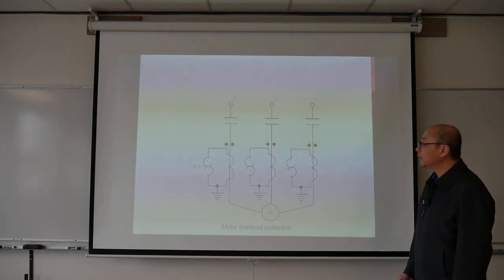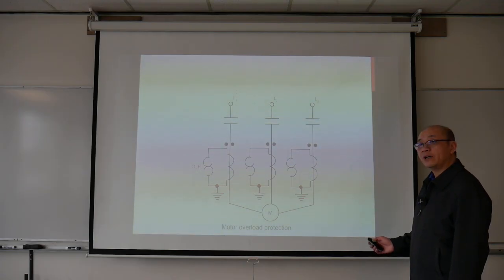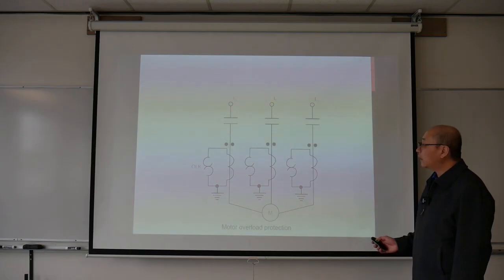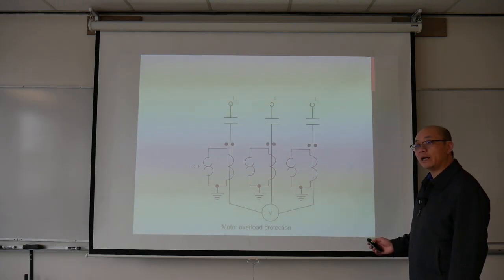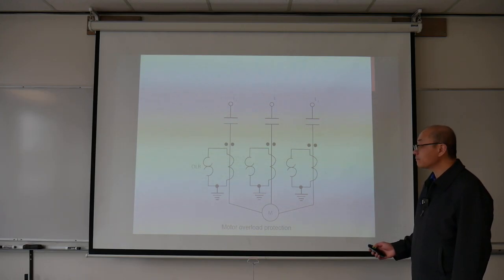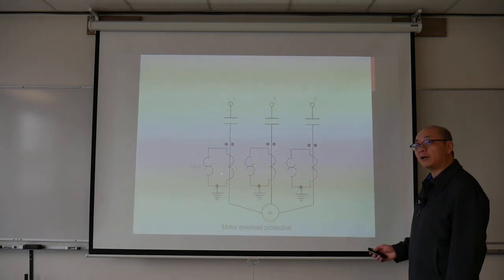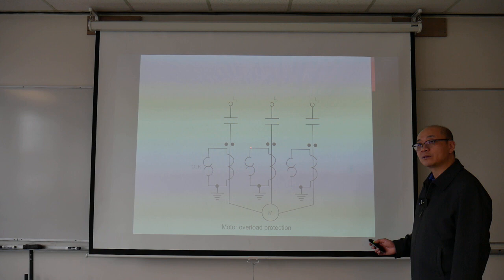This picture shows us using current transformers in a three-phase motor. Say this is a very large three-phase motor, let's say 200 horsepower. The overload protection, the overload heater for a 200 horsepower motor, will be very big and bulky. It's going to occupy lots of space. So if we put a current transformer in there to reduce the current to a fairly small value, then we can use a much smaller overload heater. We can still provide protection for this 200 horsepower motor by using a smaller overload heater with overload relay protection.